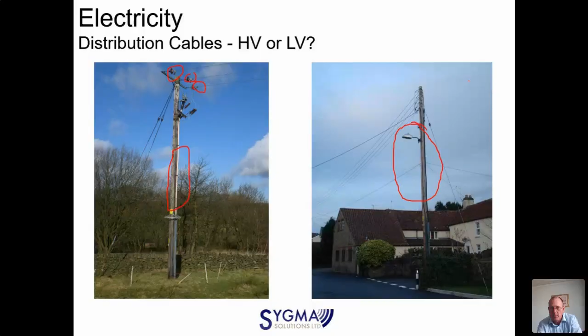On this side, there's 2 things that immediately give it away besides the configuration of the overhead: street lighting and BT. You cannot have BT or street furniture on an HV pole in this country - it's illegal. You can have LV and HV on the same pole, but not other services like BT. So there's BT on it. And again, from a surveyor's point of view, if you look closely there's a whole load of cables disappearing underground.